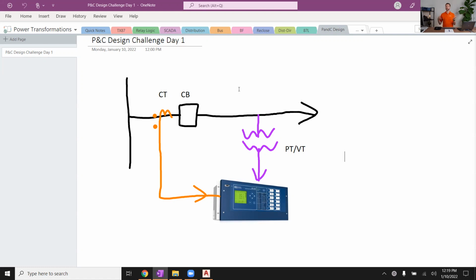So we bring in these currents and these voltages to our relay, our protective relay, and then the relay processes those and determines whether there's something wrong, whether there's a fault, an abnormal condition on the power system. It makes a decision. If this is a fault, it needs to take automated action to clear or isolate that fault. And so it's going to send some signals out from the relay to the circuit breaker. And we're going to draw those here.